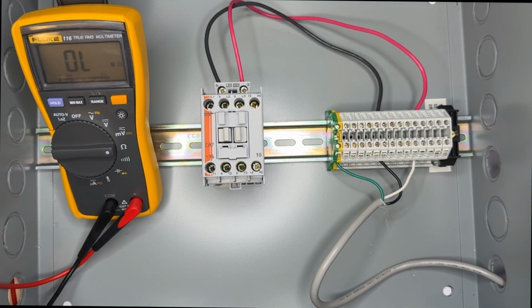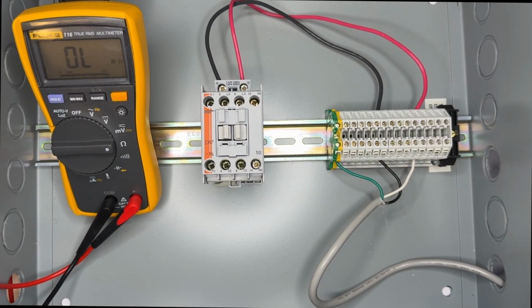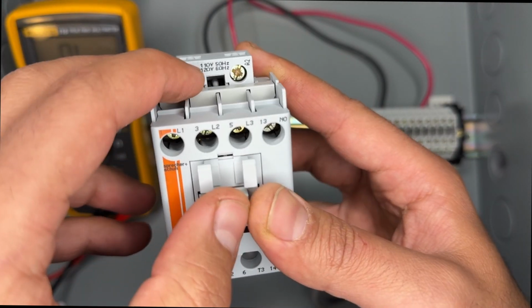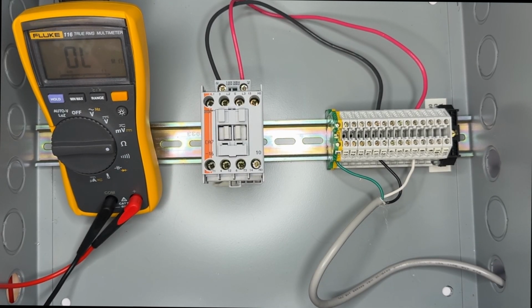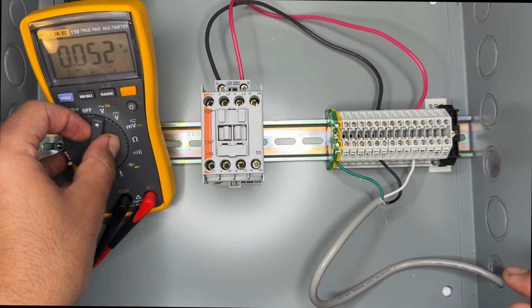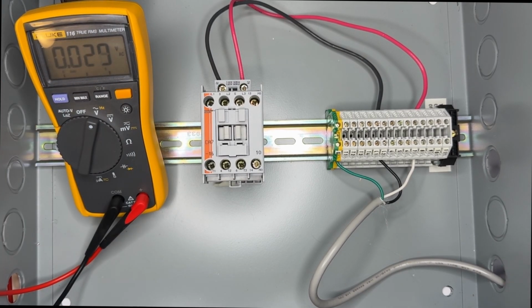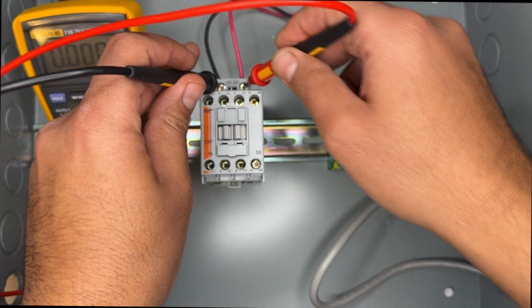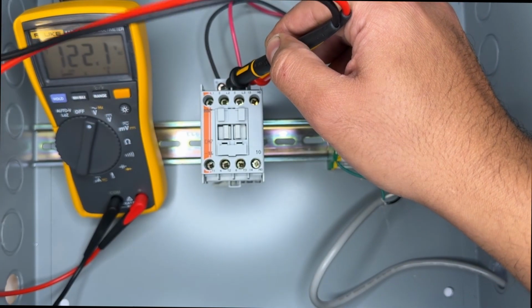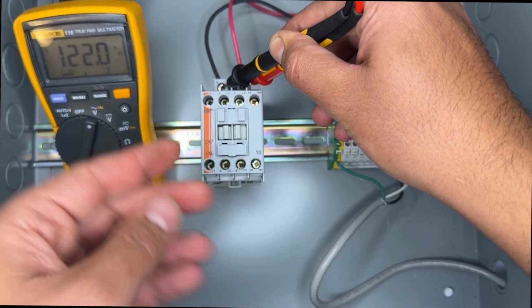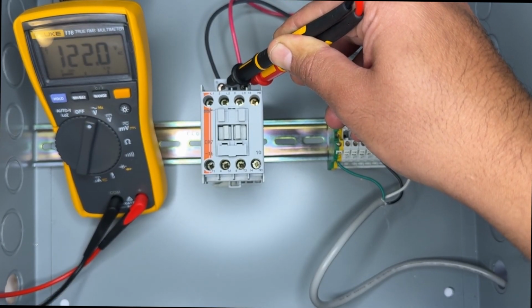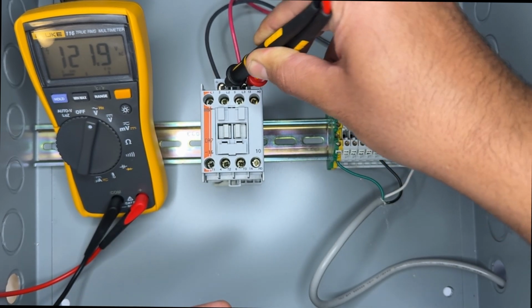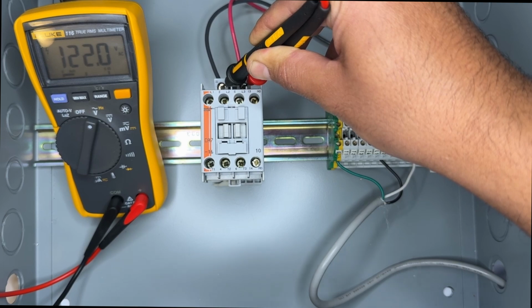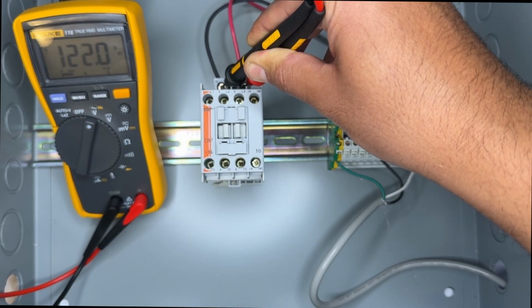So the next test we want to do now, we're going to test with power. So again, you want to look up your coil voltage in this case. So this one runs on 110 or 120. So let's go ahead and apply voltage. You're going to see the plunger pull in, and we're going to set our meter to volts AC. Make sure you're not testing for resistance there. And let's check across here, and we've got 120, so we've got the right voltage, and the plunger has pulled in, so that is working as it should. Now if you test and you have the right voltage across your coil, but the plunger is still not pulling in, now that likely indicates that there is an issue with your coil.